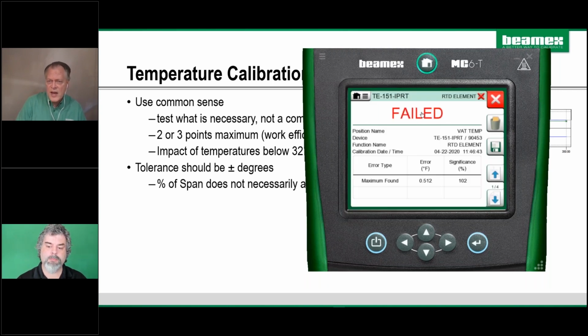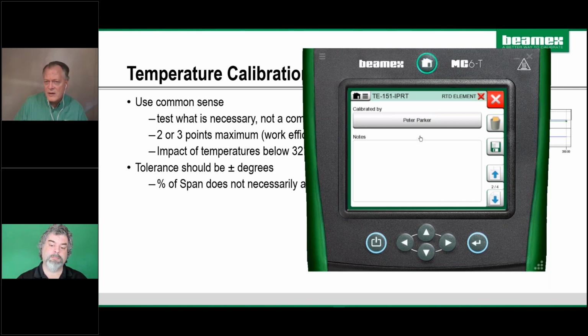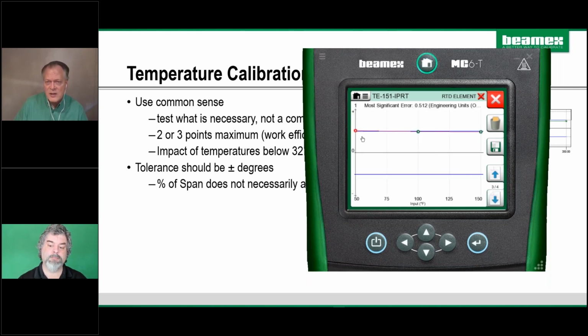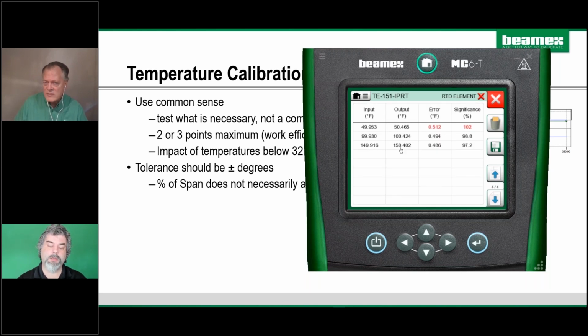So it did just record those last readings. My max error occurred there at 0. It was 0.512. It was 102% above the tolerance. And here I have Peter Parker as my technician, and I can look at the graph. So there's the data that was just observed by the dry block. So you could be writing this stuff down, recording it however you need to record it.